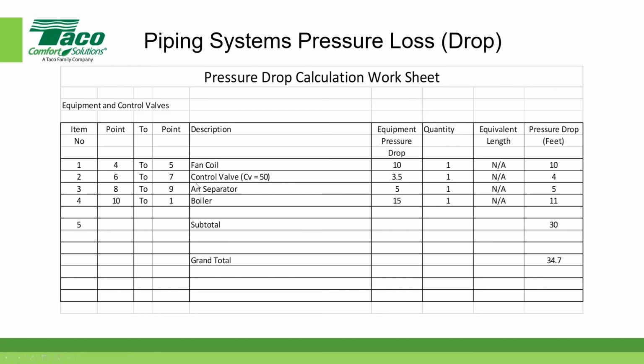Okay, and again, highlighting the control valve, the manufacturer publishes the CV value for the control valve. In this case, the CV was 50, and that says that it has a 1 pound per square inch pressure drop at 50 gallons per minute, but our system is 61.5, so I have to adjust that for the actual flow across this control valve.